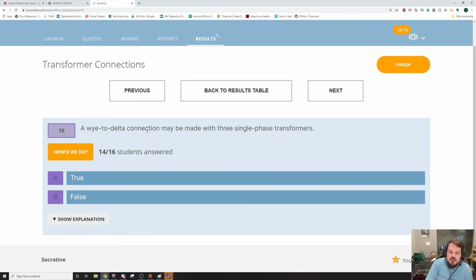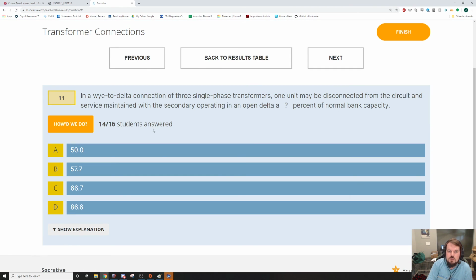A Y to delta connection may be made with 3 single-phase transformers. Yes, that's how it's normally done. In a Y to delta connection of 3 single-phase transformers, one unit may be disconnected. So, yes, you can disconnect one unit and make an open delta.